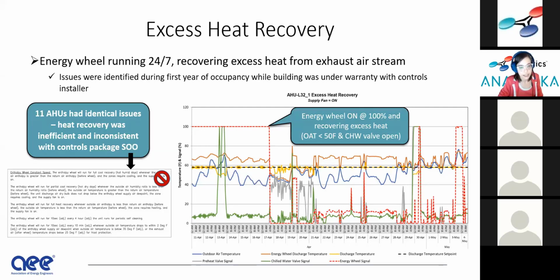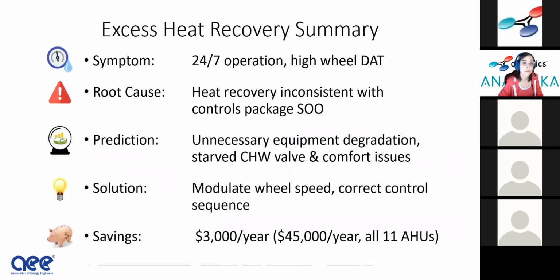Anyway, you see here, the valve was shut down for repair, and it modulates here. We're still seeing excess heat, and here we're starting to get into cool recovery mode. So this is one of the more complex issues that we find in terms of control sequences, but pretty straightforward still. 11 air handlers had identical problems like this. So a whole bank, if you want to call it that, of air handlers didn't have their heat recovery working. That's significant. Imagine if you don't find that for 2 years and now nobody knows whose fault it is or the root cause. And it's not about the fault, but it's about repairing it under that warranty, identifying it then.